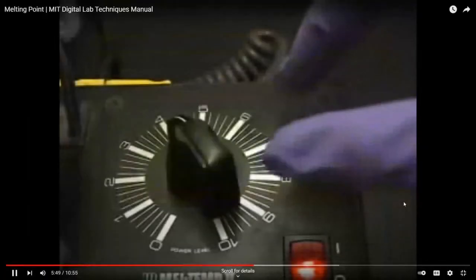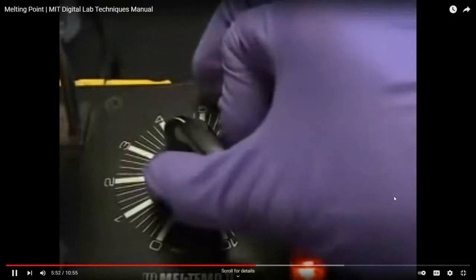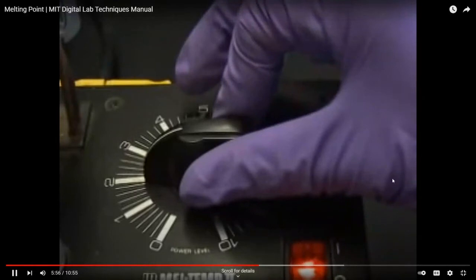After the temperature is within 20 degrees Celsius of the expected melting point, dial down the voltage so that the temperature increases at a rate of 1 to 2 degrees Celsius per minute. Yeah, you can feel what's going on, right? Say you are riding a horse. When your destination is far, you really run fast.